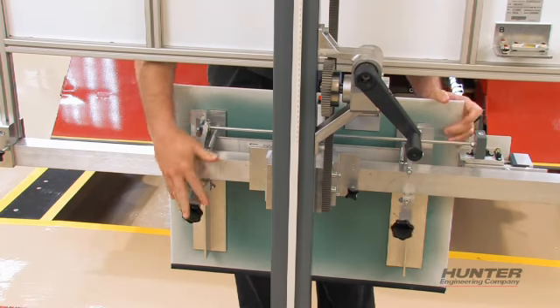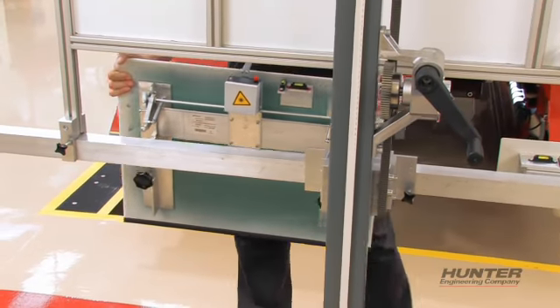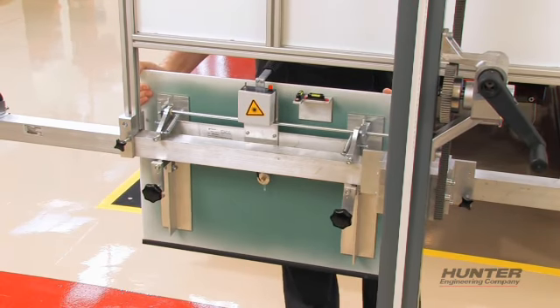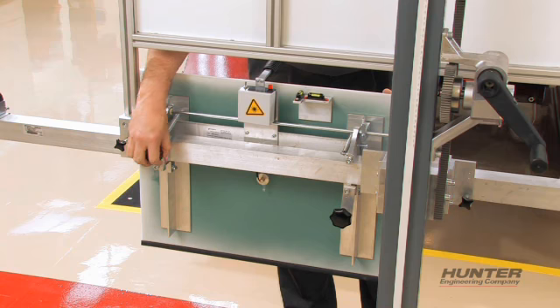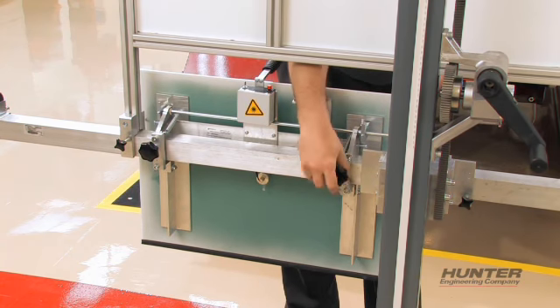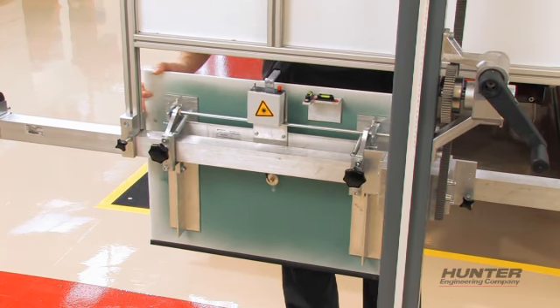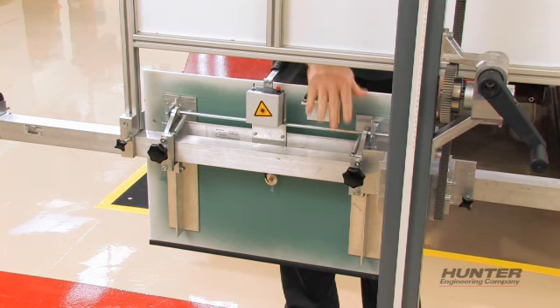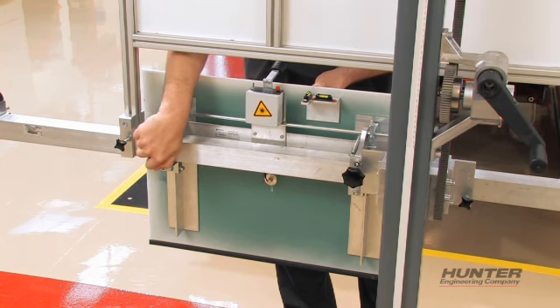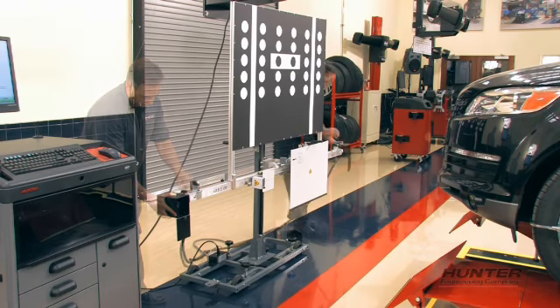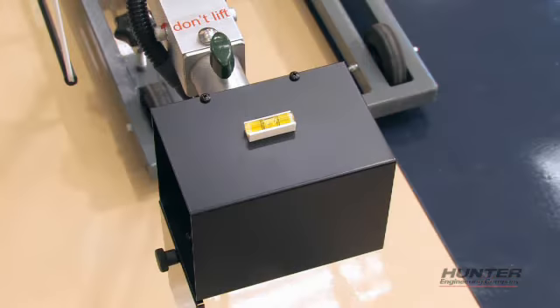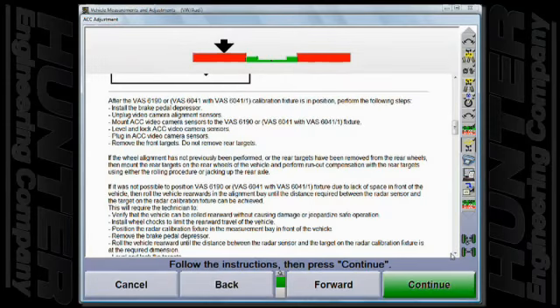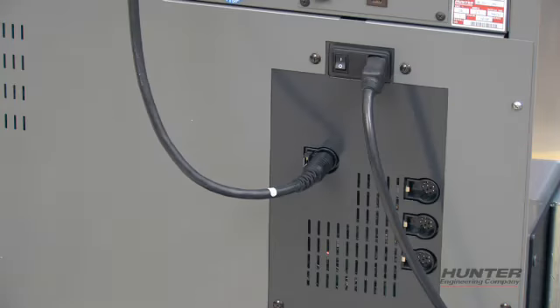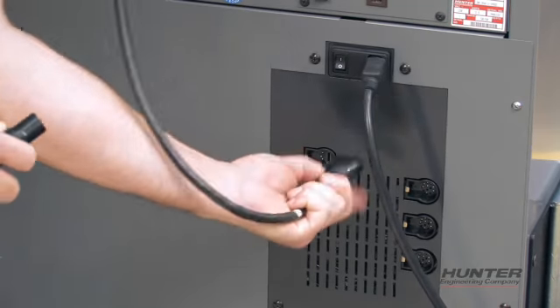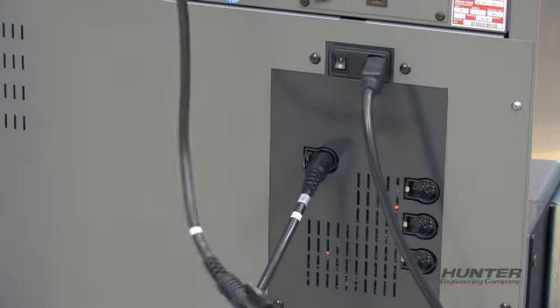If prompted, move the mirror assembly from the middle of the fixture to the right of the vertical slide. Position the mirror assembly bracket against the vertical slide bracket and snug the lock knobs. Otherwise, leave it centered on the calibration bar. Mount the aiming cameras to the calibration bar on each side and lock them level. When prompted to do so, disconnect the alignment cameras from the back of the console and connect the aiming cameras.